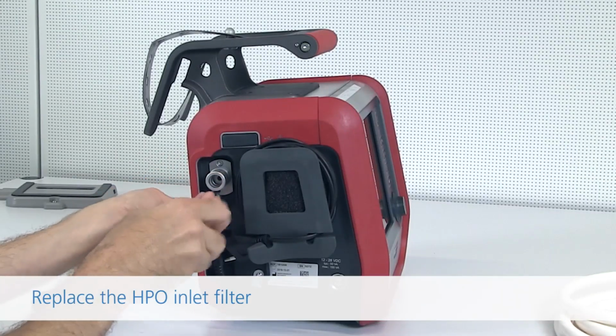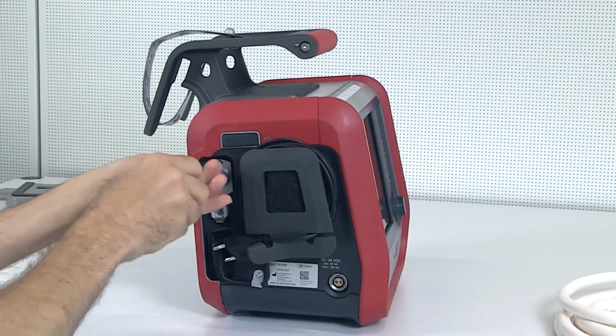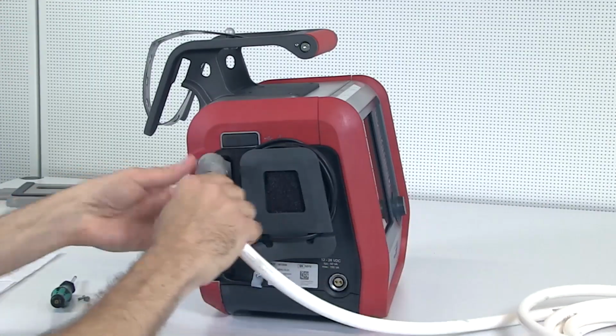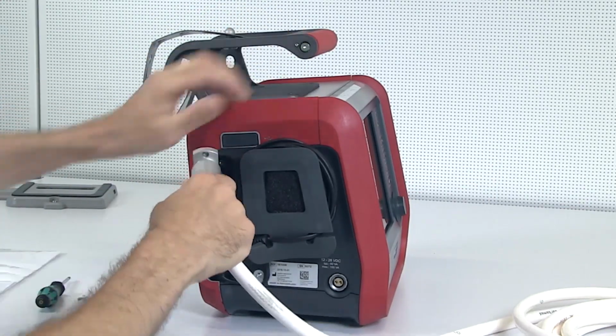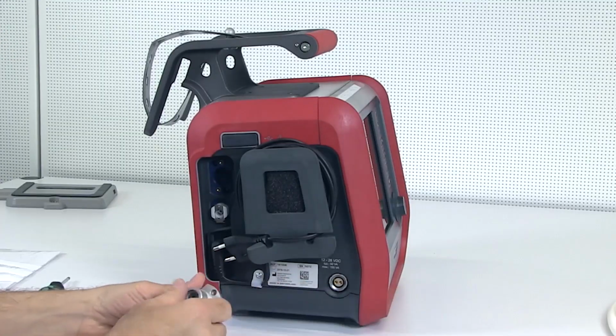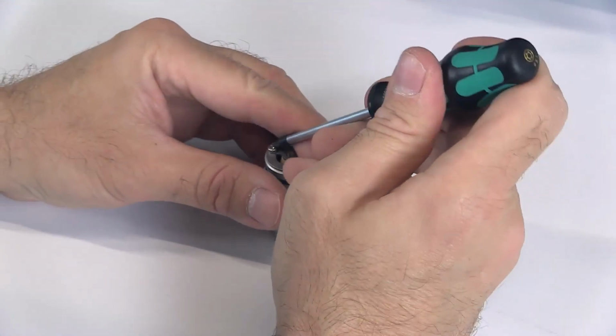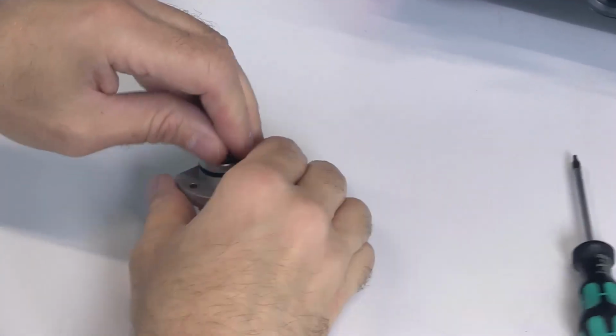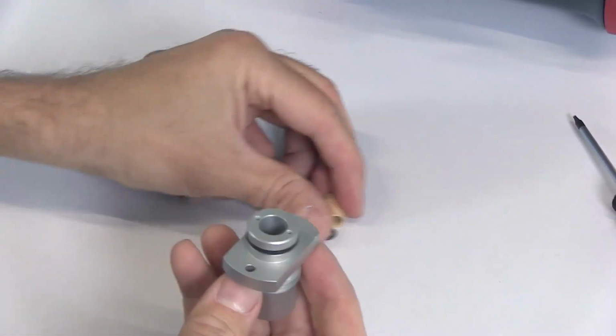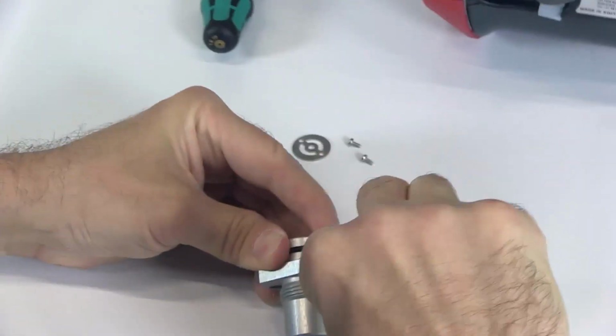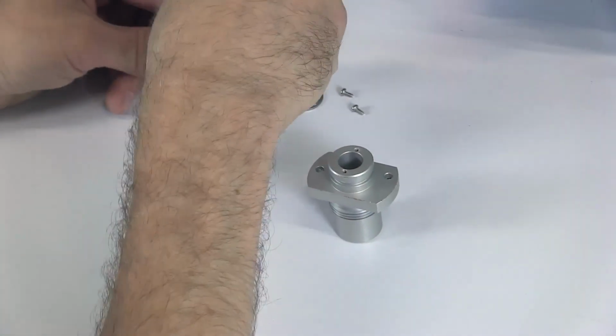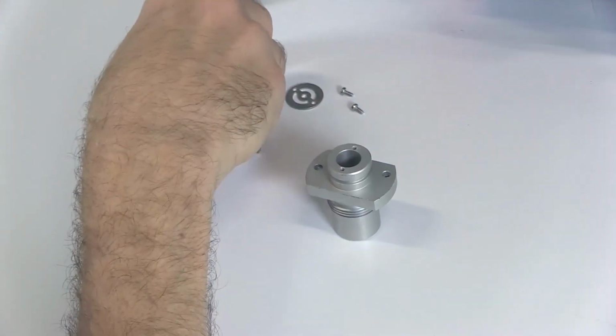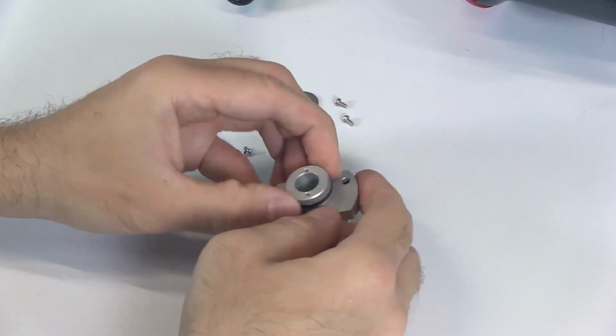Remove the high-pressure oxygen adapter. To make removal of the oxygen adapter easier, use the oxygen hose to engage the adapter and then remove it. Remove the filter holder plate. Replace the HPO inlet filter and the two O-rings. If necessary, replace the screws as well. Assemble the HPO filter, then install the oxygen adapter on the ventilator unit.